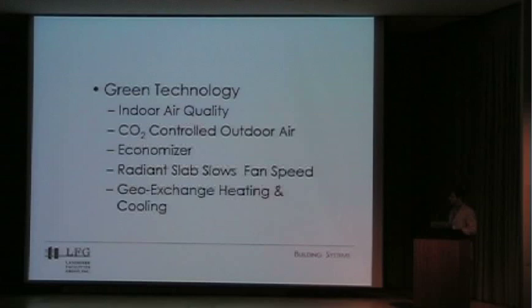All of the outdoor air and ventilation load is controlled based on CO2 sensors. The building monitors the level of CO2 produced by the number of people inside the space, and as the CO2 level rises, it knows it needs more outside air because it needs more oxygen - these people are falling asleep. So it starts pumping in more outside air and increases how much air is exchanging through the building. Then as people leave, the CO2 levels go back down, and the building can slowly close the outside air intakes, only using as much energy as it needs for that particular moment.